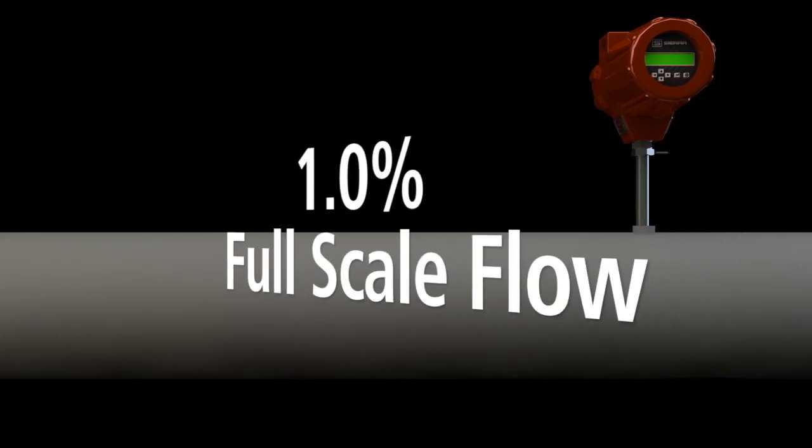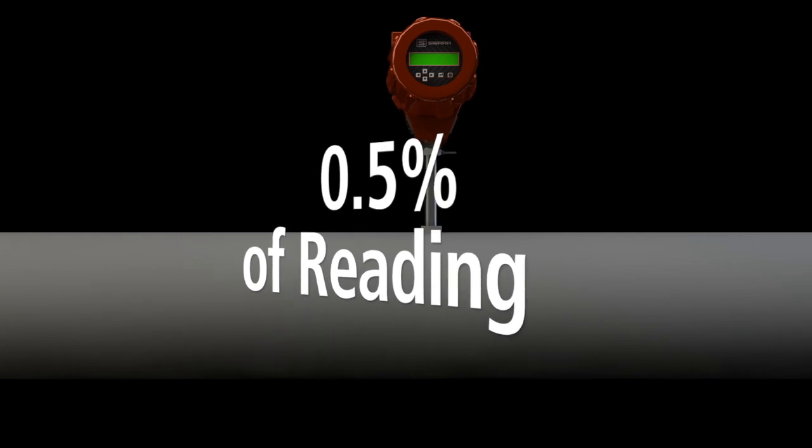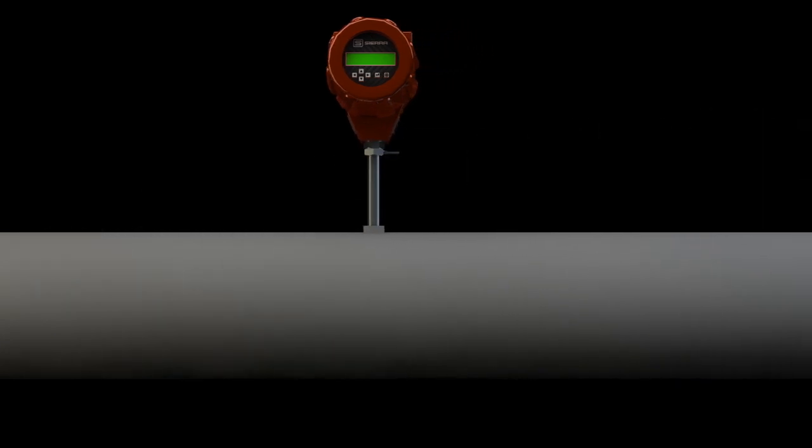Standard accuracy is 1% of full-scale flow, but recent innovation, as with Sierra's four-sensor QuadraTherm thermal meter, has pushed accuracy to 0.5% of reading, rivaling that of Coriolis meters.